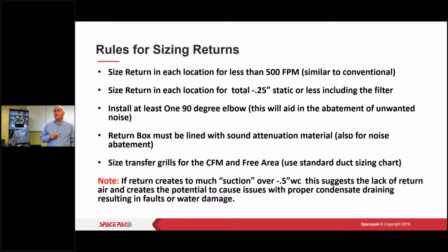So what does it say there on that note? If return creates too much suction over 0.5 inches water column, this suggests a lack of return air and creates a potential to cause issues with proper condensate draining, resulting in faults or water damage. So make sure you get your return proper.